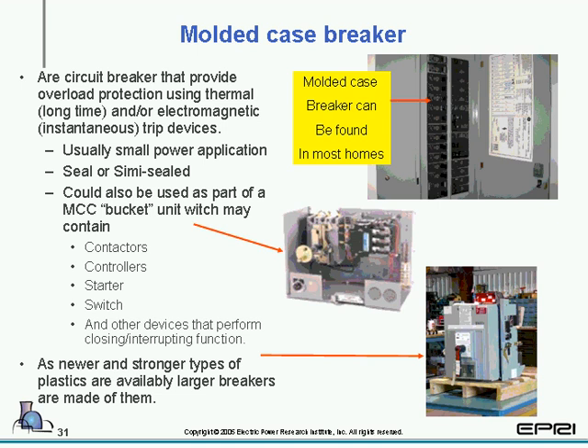Usually small powered applications, sealed or semi-sealed, and could also be used as part of an MCC or bucket unit, which may contain, and we have a list of items such as contactors, controllers, starters, switches, and so on. And the last item we have, as newer and stronger types of plastics are available, large breakers being made of them. We use the word plastics loosely, because it may be plastic or some other type of material. The basic idea is they are typically sealed or semi-sealed.